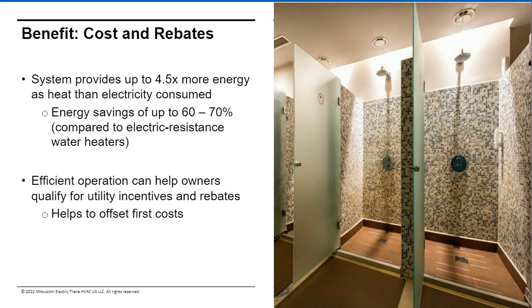As compared to an all-electric water heater, CO2-based domestic hot water systems offer up to 4.5 times the efficiency. Blended or seasonal efficiencies will vary with the ASHRAE climate zone for the installation location and other factors, but the end result will inevitably be multiple times the efficiency of an electric water heater. Several cities and states across the country have mandated all-electric domestic hot water solutions for new construction, and some of them also apply to retrofit applications. Many of these jurisdictions offer incentives to offset the first cost of implementing a heat pump water heater solution. And after the hurdle of first cost has been crossed, operating cost is similar to that of a gas-fired domestic hot water system, and sometimes even less.